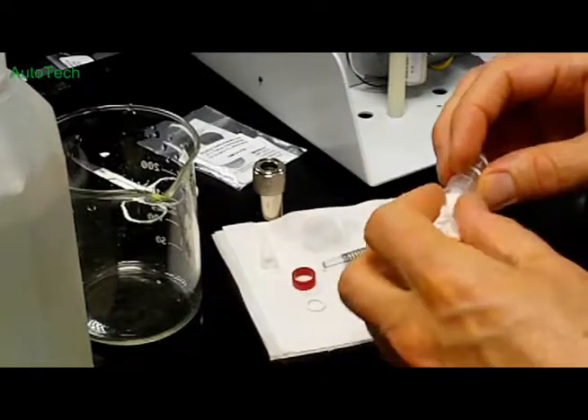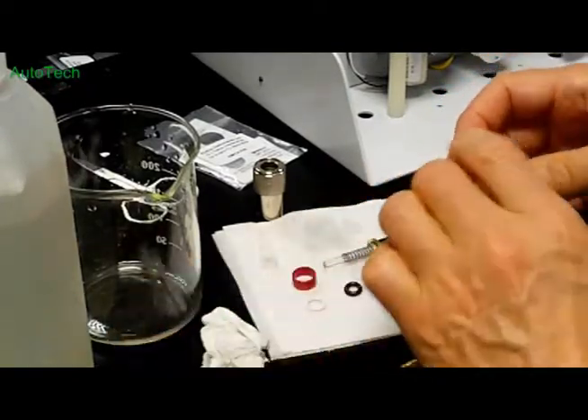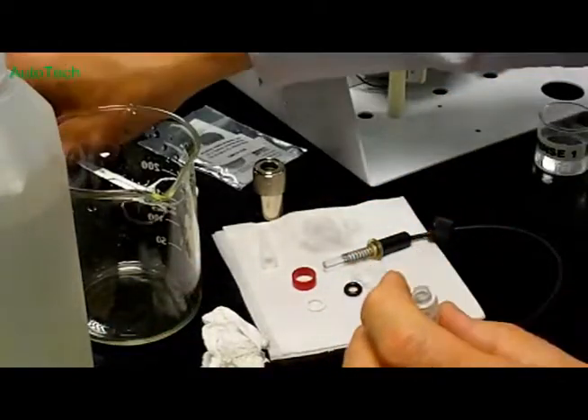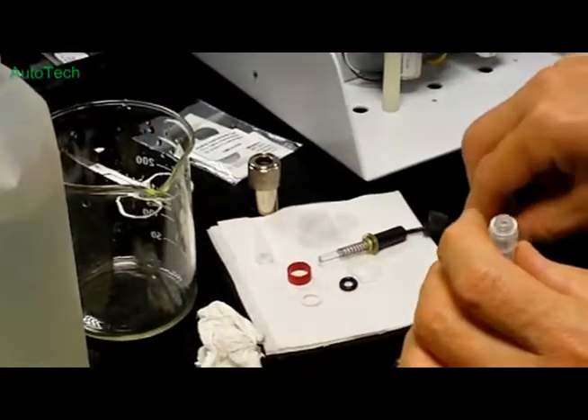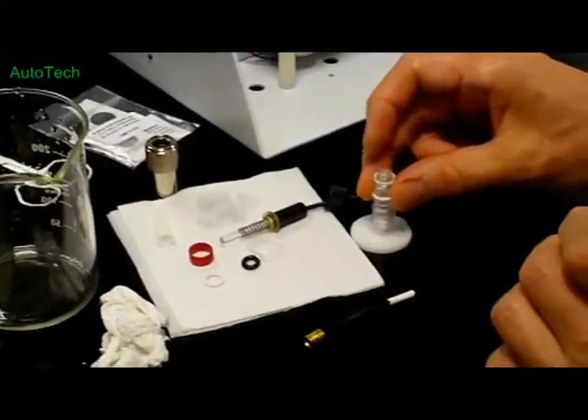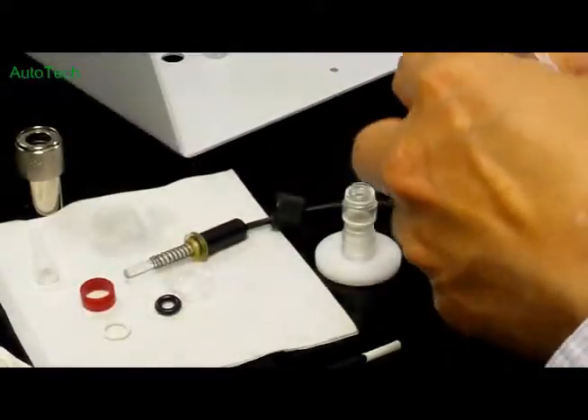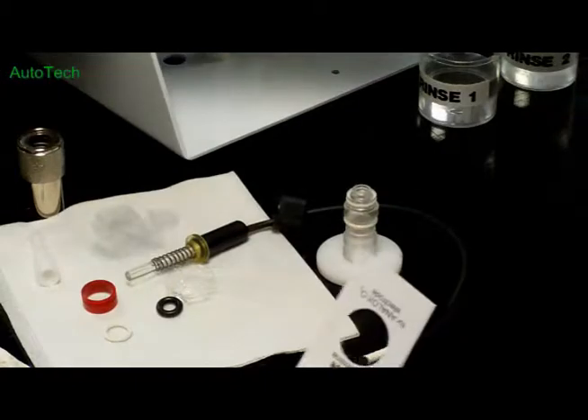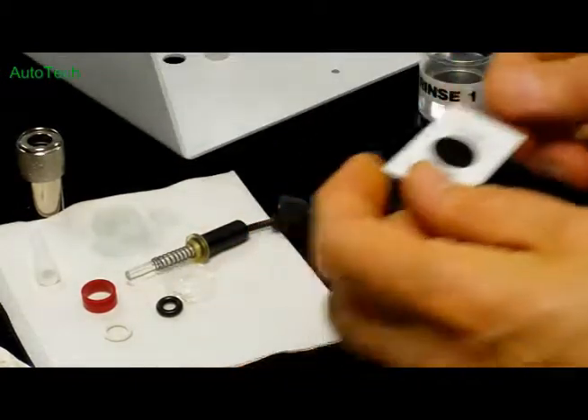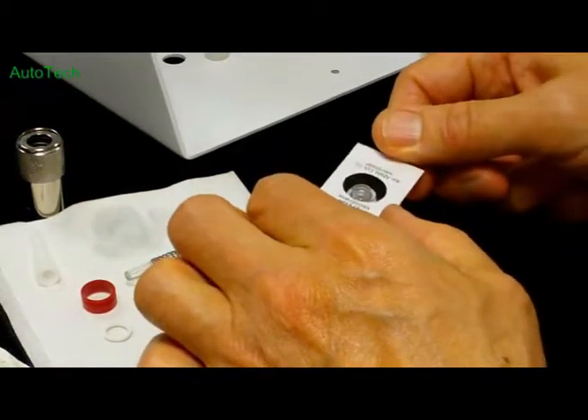And so now we're ready for reassembly. So we'll take the electrode jacket stand, place the jacket on the stand, take a new membrane, and position this on the end of the jacket.